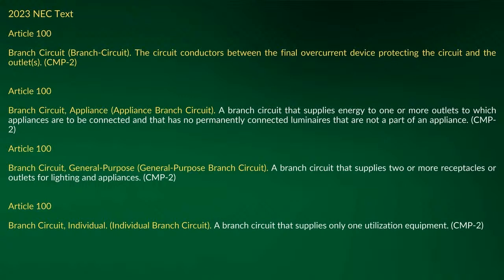Now, if you look at an appliance branch circuit, it says a branch circuit that supplies energy to one or more outlets to which appliances are to be connected and that has no permanently connected luminaires that are not part of the appliance. What I'm going to contend here is this is where your cord-and-plug connecting stuff applies. This isn't for hardwired. That's not what an appliance branch circuit is.